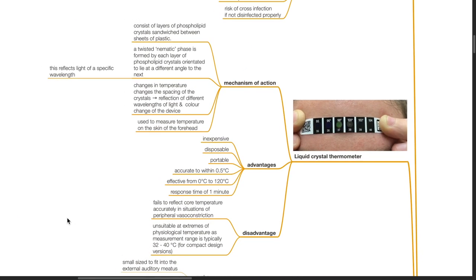Liquid crystal thermometers consist of layers of phospholipid crystals sandwiched between sheets of plastic. A twisted nematic phase is formed by each layer of phospholipid crystals oriented to lie at a different angle to the next, reflecting light at a specific wavelength. Changes in temperature alter the spacing of the crystals and the reflection of different wavelengths of light, causing a color change. They are used to measure temperature on the skin of the forehead. Advantages: inexpensive, disposable, portable, accurate within ±0.5 degrees Celsius, effective from 0 to 120 degrees Celsius, with a response time of 1 minute. Disadvantages: they fail to reflect core temperature accurately in situations of peripheral vasoconstriction and are unsuitable at extremes of physiological temperature, with a typical measurement range of 32 to 40 degrees Celsius.